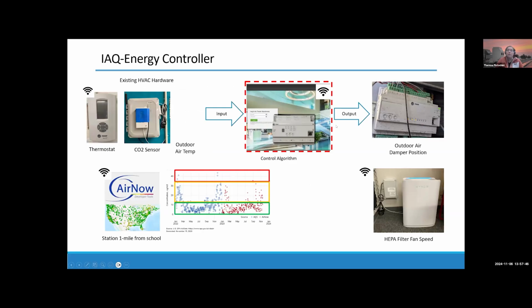Basically, we took a Trane building management energy system already existing. We added an internet connection. We used the existing internet connection to pull data from the AirNow network over the internet. So we don't have to add any PM 2.5 sensors. We just grab that data from the internet. That feeds into the control algorithm. We added a CO2 sensor that feeds into the control algorithm, and we adjust the existing outdoor air damper. We also added this internet connected portable air cleaner. And again, it's receiving all its commands over the internet and operating sort of seamlessly. And so that is it.